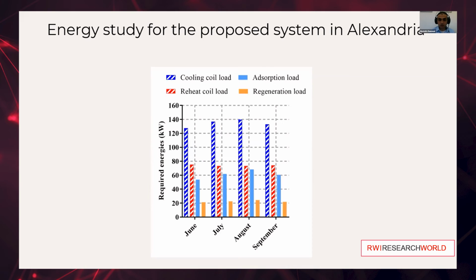From the graph, it's obvious that August represents the peak load month. This is due to the high latent load during this month. Also, the figure shows that the proposed system requires less energy than the traditional one. This is due to the dependence of the proposed system on desiccant material to handle latent load, rather than dependence on condensation and deep cooling to remove the latent load.